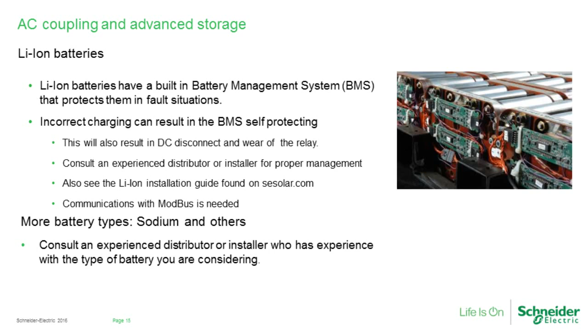So we touched on this already, but it's worth reiterating. What do we expect from a system? During normal operation, the Conext SW or XW Plus is simply going to be in pass-through. There's going to be a little bit of float charge on the batteries, and depending on the technology of the batteries, they have different self-discharge rates, which describes how much you need to put back into those batteries every day to maintain that storage.